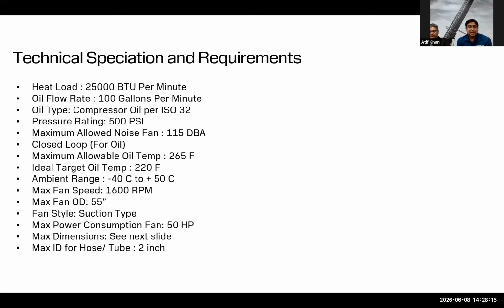The fan speed. This cooling system is designed with an air fan, and we want it to operate at no more than 1600 RPM because that helps with lesser noise and lesser power consumption, and higher speed fans can be riskier to work with. The fan diameter is largely based on the real estate availability, nothing more than that. The fan style that we currently use is a suction type. What that means is that we are sucking fresh air from the atmosphere, but not blowing it over the heat exchanger. Rather, we allow the air to pass through those cores first, and then that air gets sucked in by the fan and thrown out again back to the atmosphere.